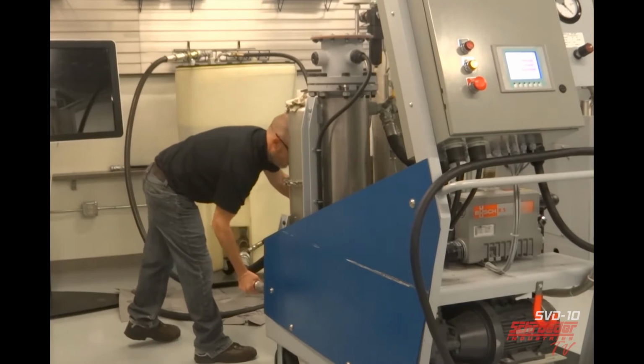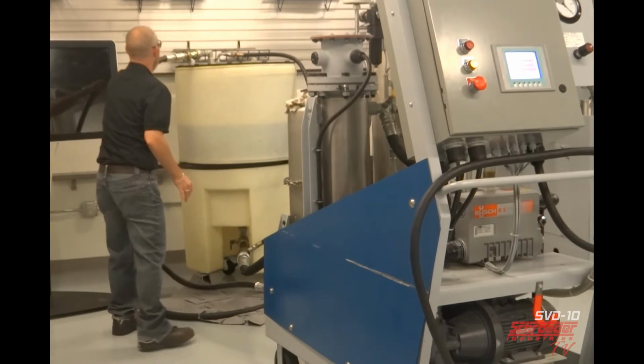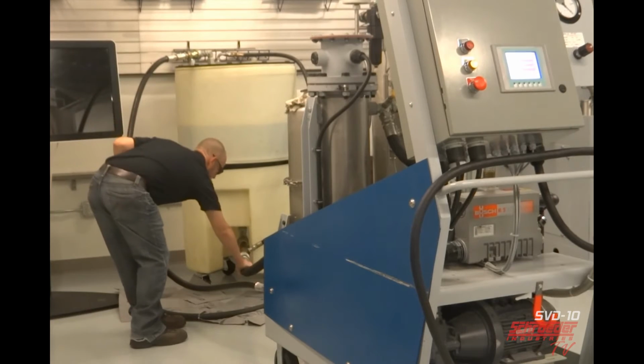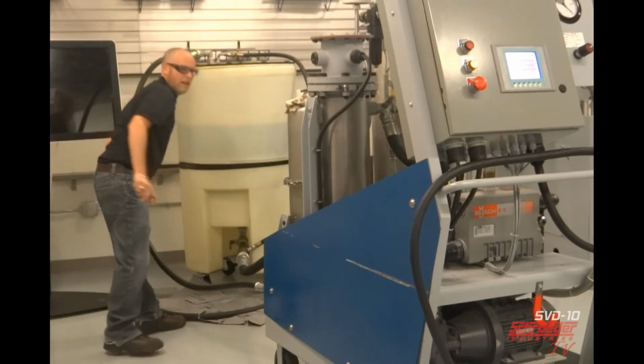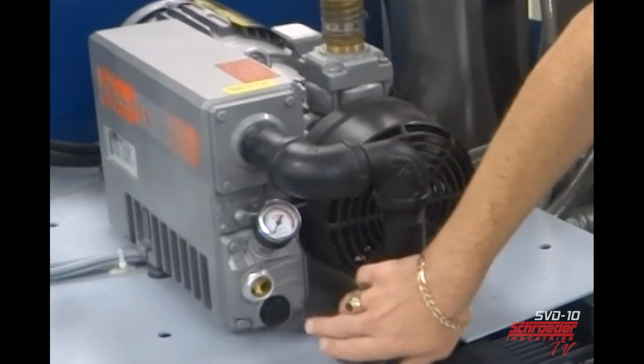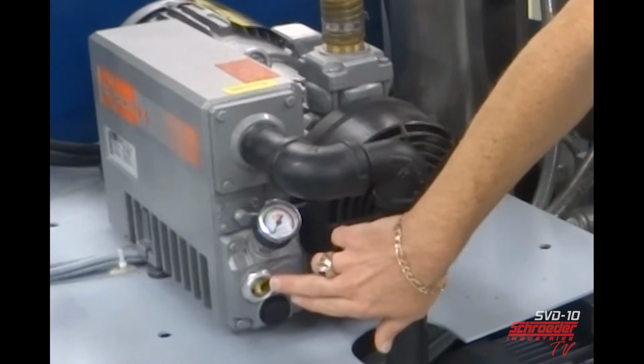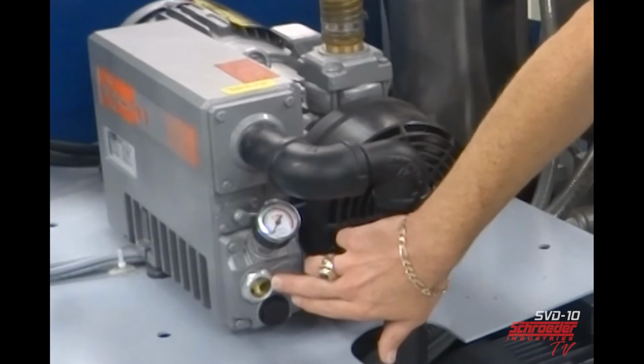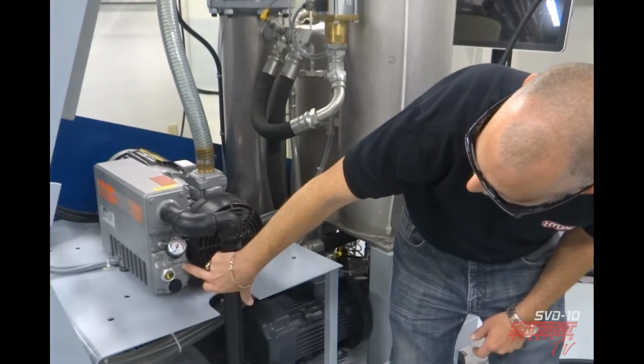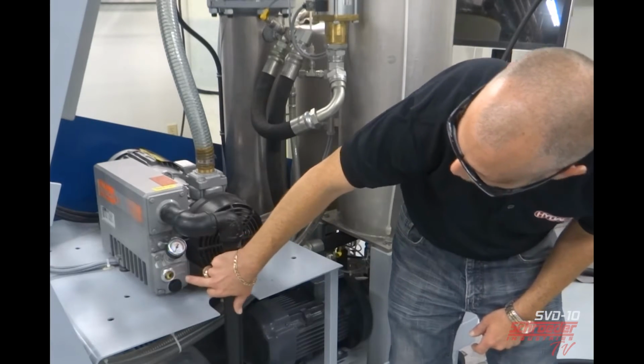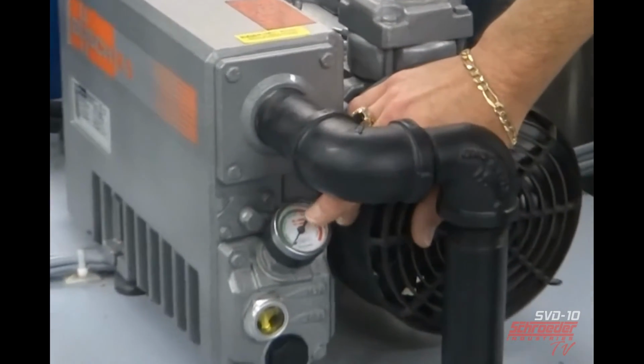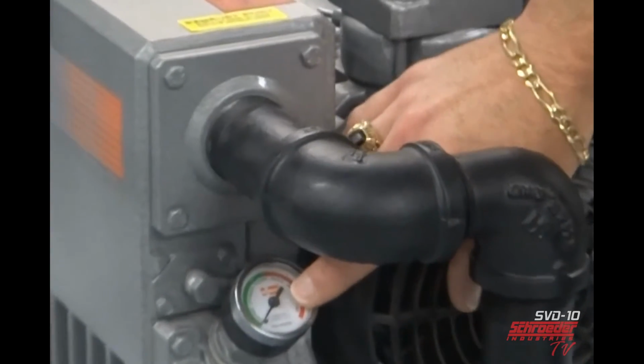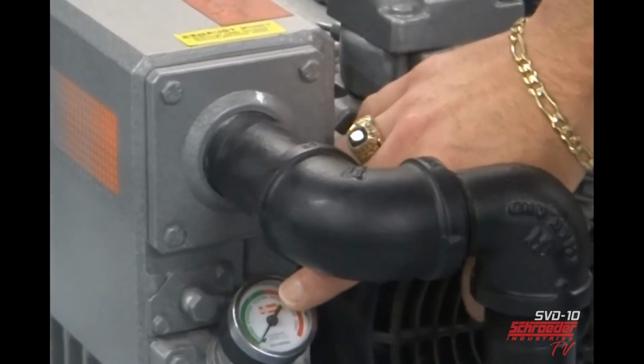Before you start the system, you want to ensure your hydraulic system connections are tight. This will prevent any leakage that may occur from a loose connection. Make sure that after every 8 hours of operation you check the oil level of the vacuum pump before you start up the SVD. There's an indicated minimum and maximum line, so it should always be full. There is also a gauge to show when you need to change the actual filter element located on the side of the vacuum pump as well.